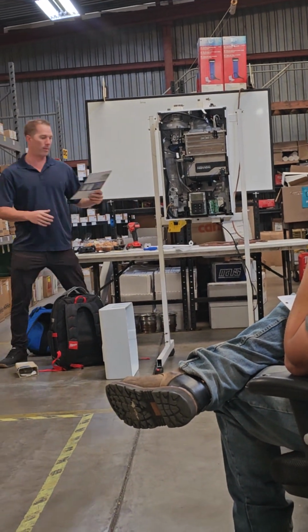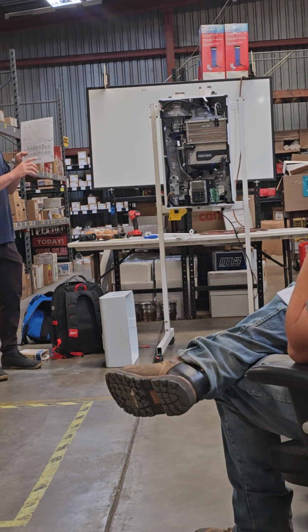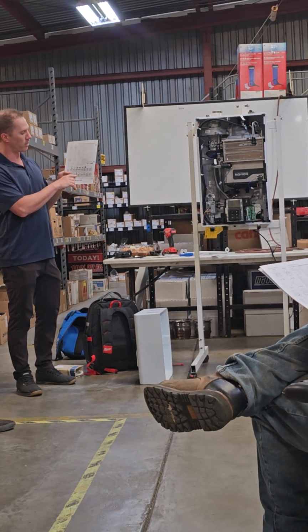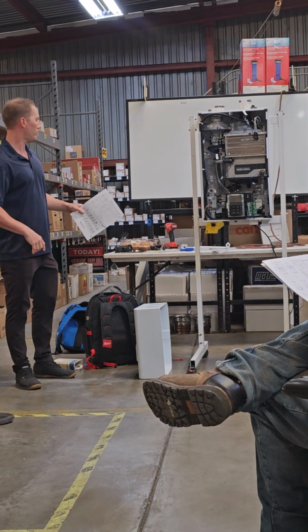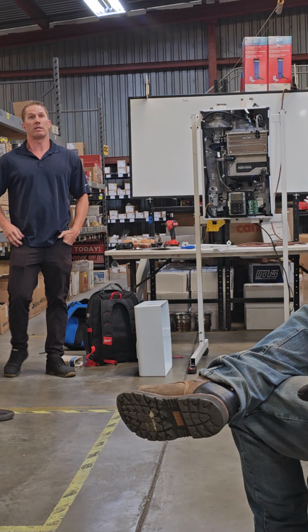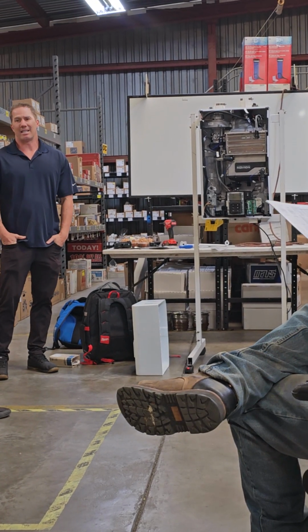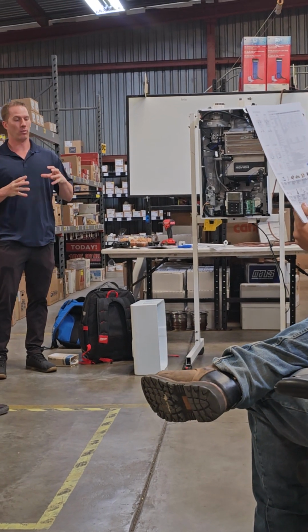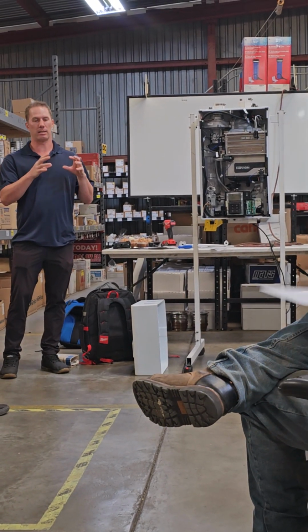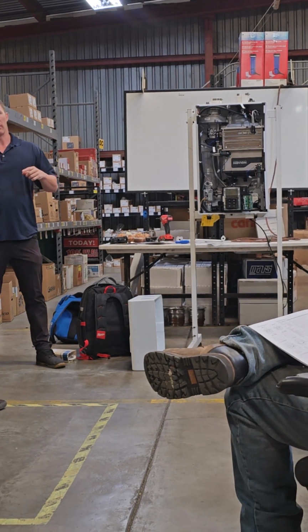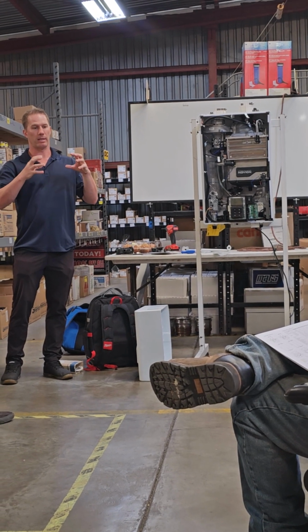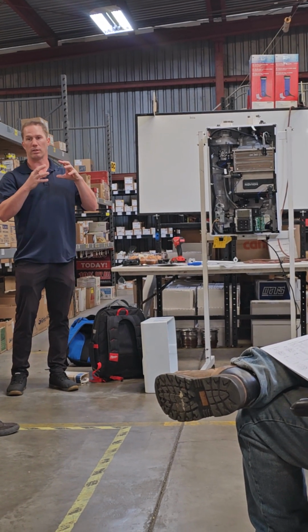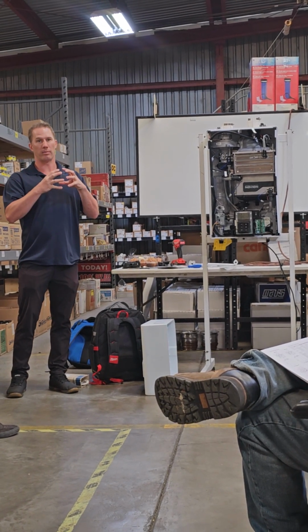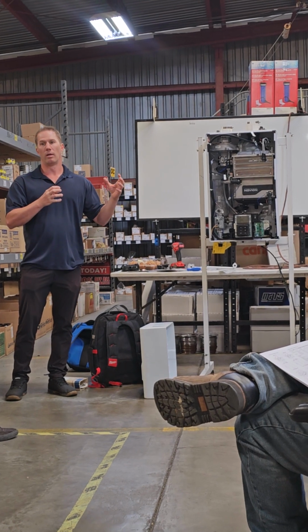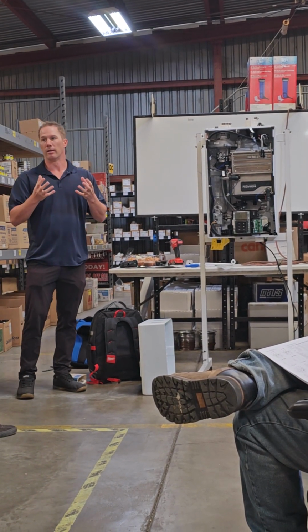There's a lot of wells up here, and Navien always recommends putting some kind of water treatment on the unit before it goes in. Navien has a peak flow system. Peak flow works great, it works up to 30 grains of hardness, and it takes out 98 to 99% of all the hardness. Basically it works off of template-assisted crystallization, it's a TAC. So there's a media, the water goes through it, and the TAC basically makes all the minerals bind to themselves.